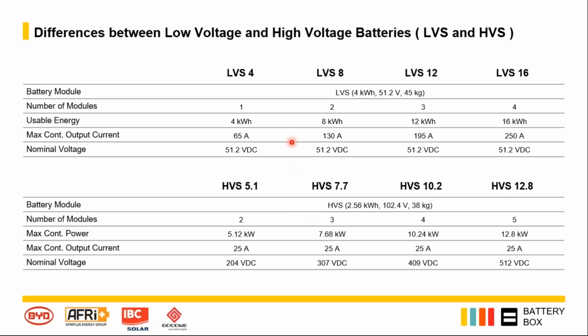So here we've got the main difference between low voltage and high voltage batteries. I'd like to cover this a little more because it gives people some idea of how to handle high voltage batteries if they've never dealt with them before. So I'm going to compare them to our LVS batteries. LVS is also a tower design where you've got modules you put in a tower. So here we've got the different towers. You have 4, 8, 12, and 16. And that's a tower of 1, 2, 3, and 4 modules respectively.